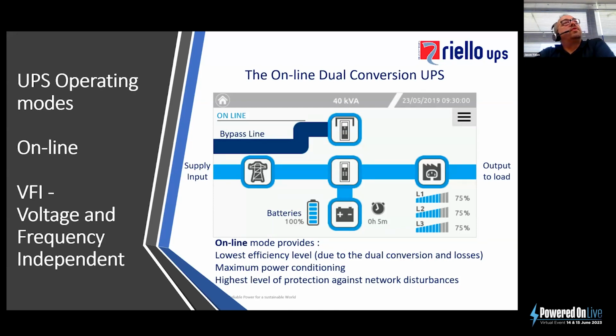The online dual conversion UPS system is so called because we take the supply from the incoming main supply, the AC, and we convert that to DC. That's our first conversion. Then we take that DC and we reinvert that back to AC again. That's referred to as our second conversion, hence the term dual conversion. The beauty of the online dual conversion UPS system is that the inverter is running permanently online, providing a clean AC waveform for the critical load, regardless of what is coming into the UPS system from the main supply.